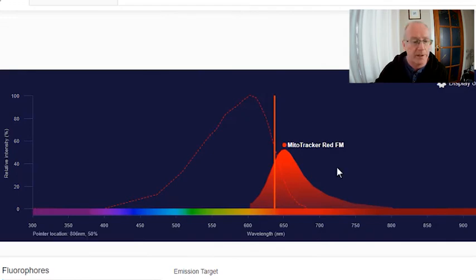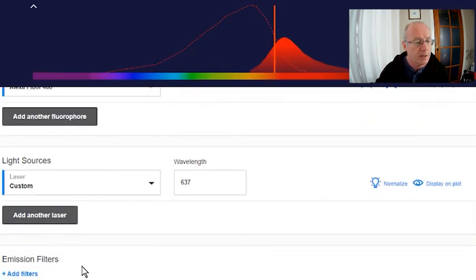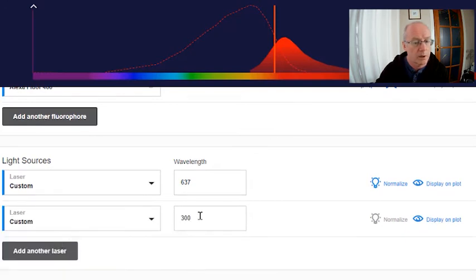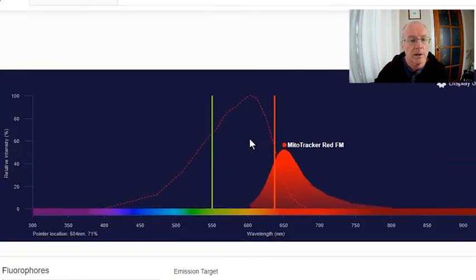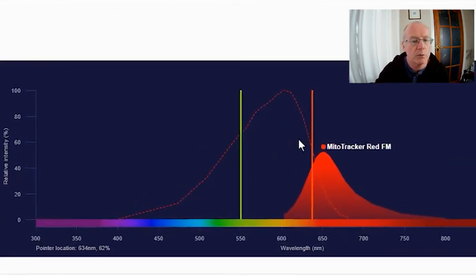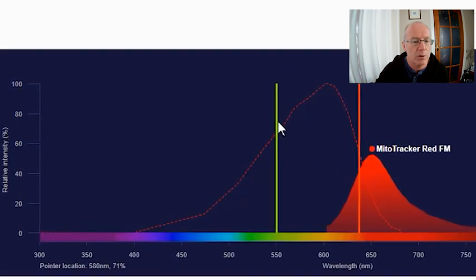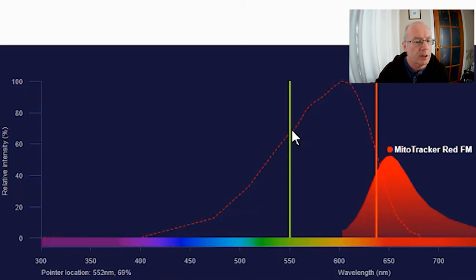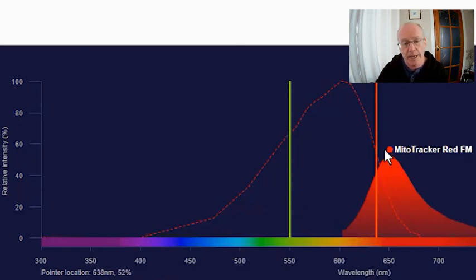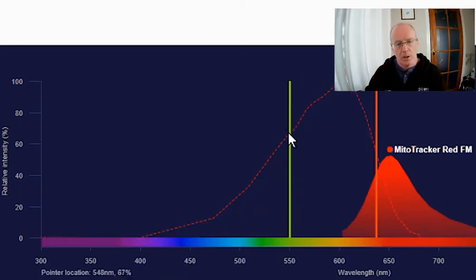So let's put a 550 in and see how that looks. So we'll add another laser. We'll just make it a custom one and make it 550. And you see there, I've got almost probably the same efficiency where you see where it cuts the spectrum. In fact, actually a little bit better here. That looks like maybe over 60% efficiency. But crucially, when you are visualizing the emission, you will hopefully not be seeing any of the excitation light.